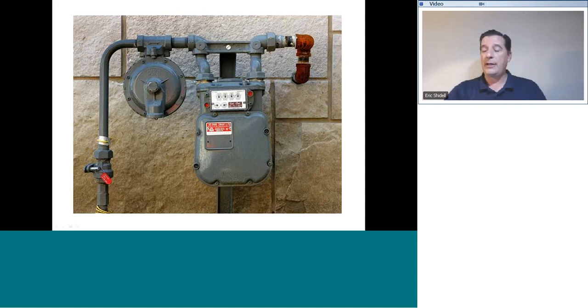The job of the regulator is to reduce the pressure from whatever the utility provider has in their line down to the pressure that will be used in the home. And if this is a home, it'll be 7 inches water column. If it's a commercial building, it may be significantly higher than that. It is this regulator's job to produce that pressure. If the pressure in the building is not appropriate, this is most likely the source of the problem. Once again, avoid the temptation to make any adjustments to this, because that is a really good way to get in trouble with the utility provider.